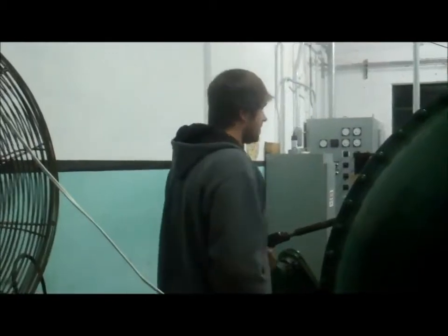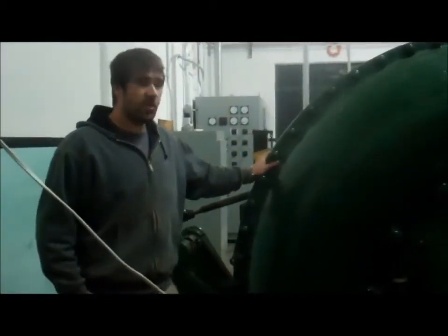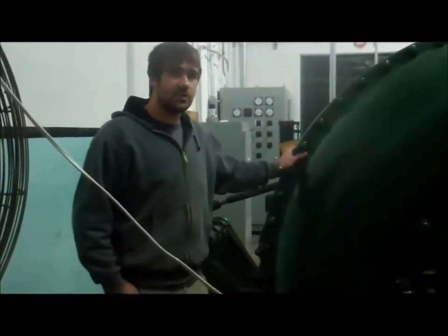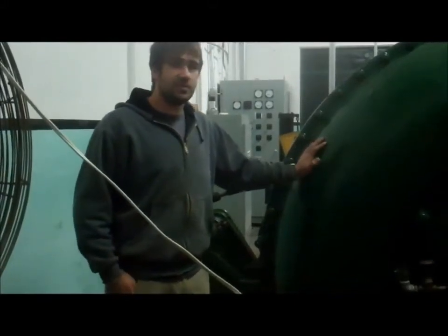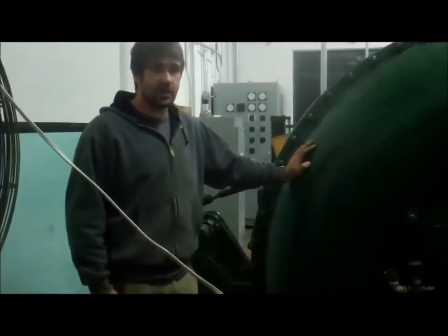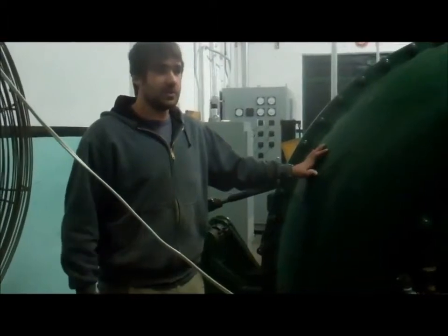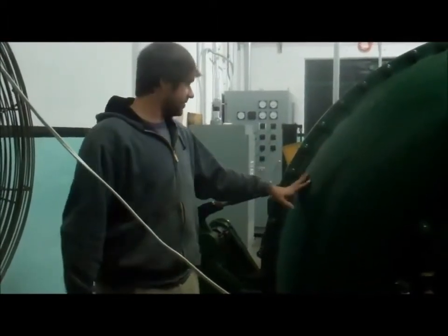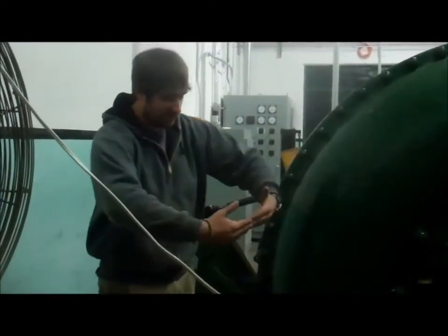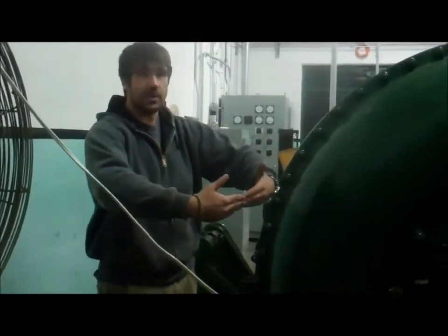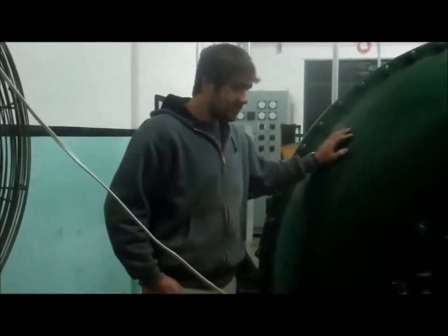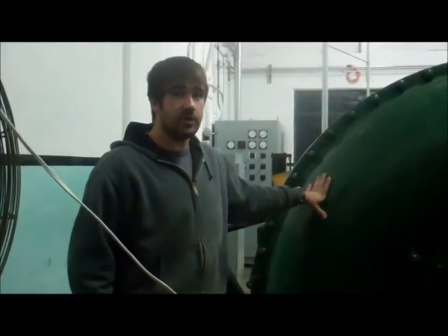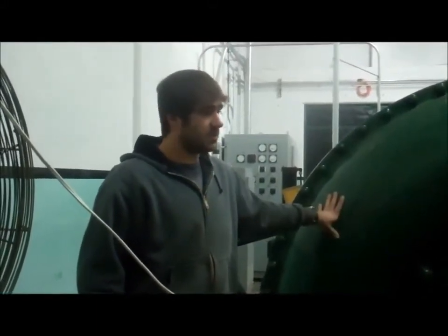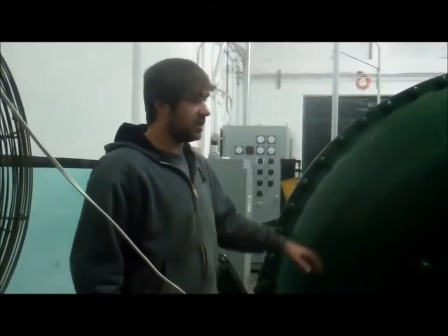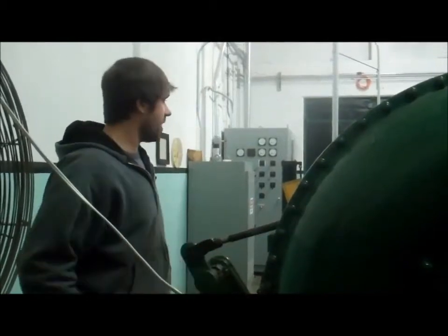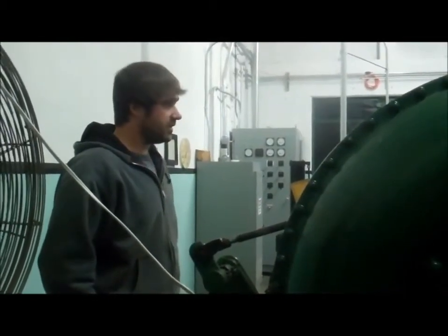It was top of the line when it came out, because the other old ones are 200 RPM machines, and this is a 600 RPM machine, which from 1910 was unheard of. And it's a Francis as well. It's only got a 21-inch diameter wheel, and it's this big, and it does 350 kW output, so 0.35 megawatts. So it puts out a lot of power for a tiny little runner, and it's very efficient.